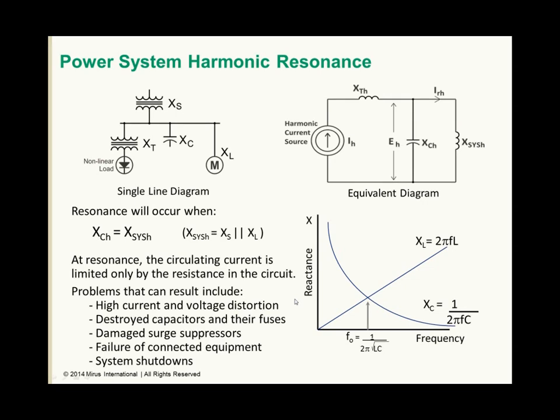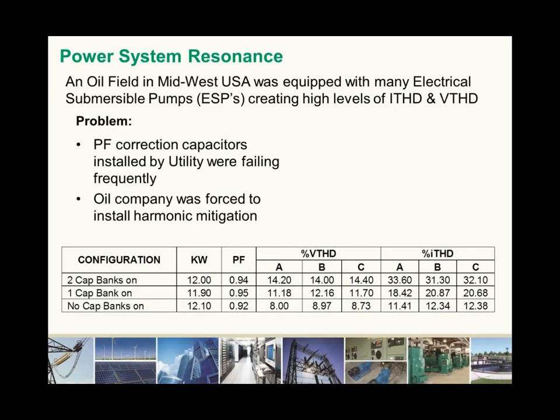An example of power system resonance is shown on this slide. Here we have an oil field in Midwest USA where they used a lot of electrical submersible pumps, or ESPs. These pumps were used to help push the oil up as the oil field was reaching its end of life, and so they're trying to get as much oil out as they could. There's not enough pressure to drive the oil up, so they were using the pumps to push water and introduce the pressure.